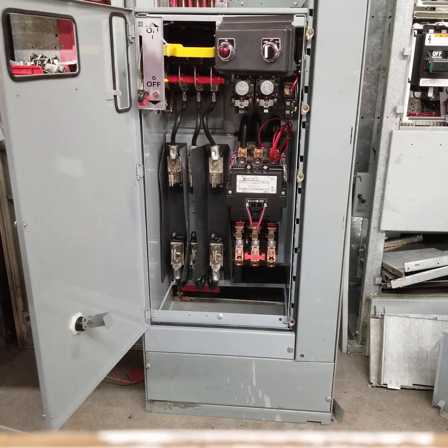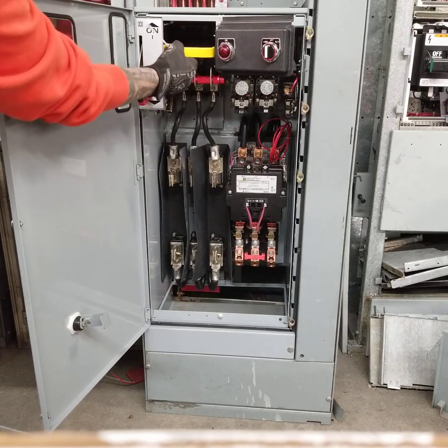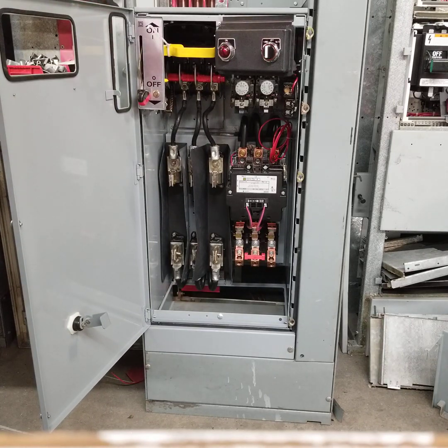With a good pull, you can see the switch actually moving — this whole base rocks back and those fingers are no longer connected to the bus bar in the cell. Now that it is free from the bus, we can proceed.